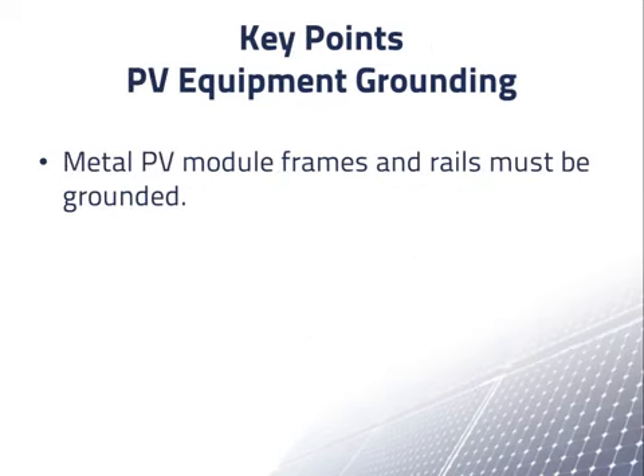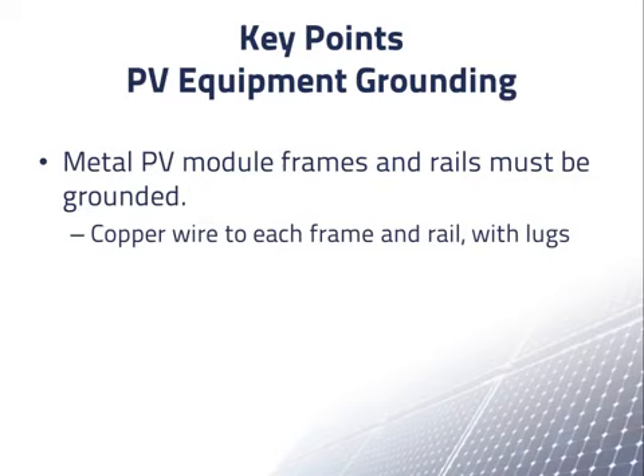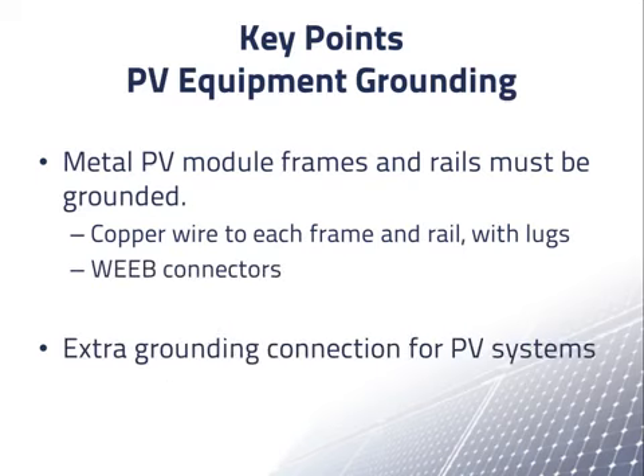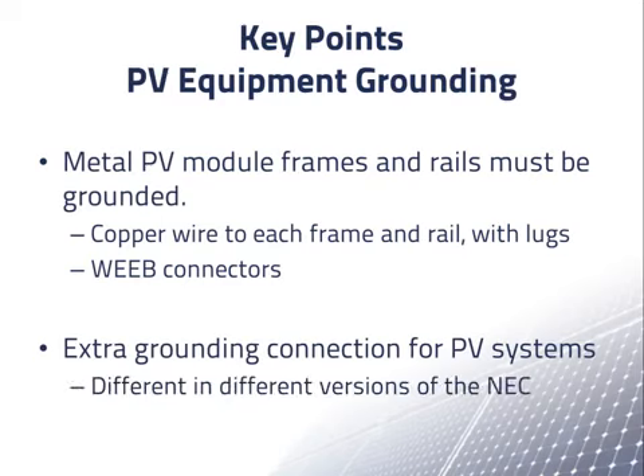In PV systems, metal PV module frames and rails must be grounded. This presents some unique challenges and some interesting solutions. The most common methods are copper wire connected to every frame and rail with an appropriate lug or WEEB connectors. The NEC also wants PV systems to have an extra grounding connection. This requirement has been different in different versions of the NEC, and future changes are likely.